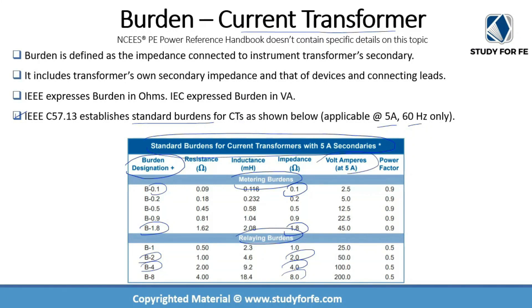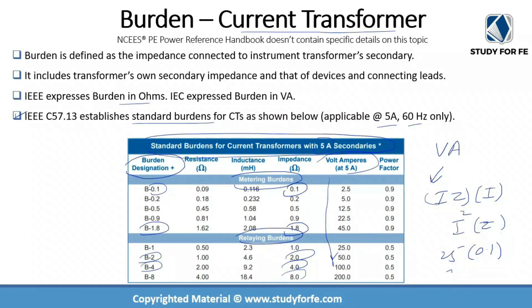IEEE expresses burden in ohms, but the table also shows volt-amperes. Volt-amperes is V·A, and since V equals I·Z, volt-amperes equals I²Z. So for a burden of 0.1 ohms, with I always equal to 5 amps, we get 5² × 0.1 = 25 × 0.1 = 2.5 VA. You can verify the remaining numbers using the same formula: VA = I²Z, substituting the appropriate impedance values.